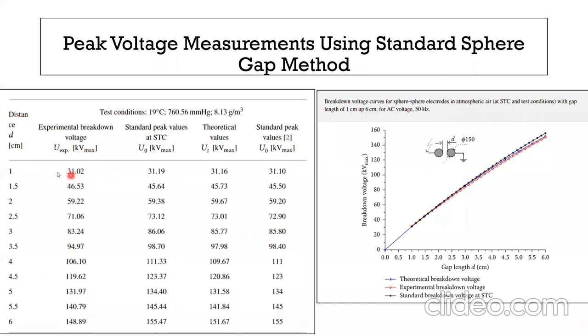That table is a lookup table already available. The manufacturer has provided you a lookup table. When you adjust the gap and when the sparking takes place, because if the gap is too large, you have applied some voltage here. If the sphere gap distance is too large, the sparking will not take place. So what you have to do is gradually push this sphere upward slowly and stop as soon as sparking takes place.